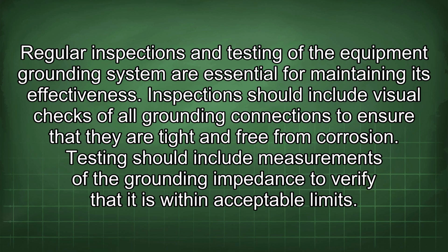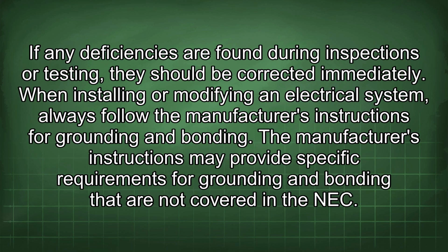Regular inspections and testing of the equipment grounding system are essential for maintaining its effectiveness. Inspections should include visual checks of all grounding connections to ensure that they are tight and free from corrosion. Testing should include measurements of the grounding impedance to verify that it is within acceptable limits. If any deficiencies are found during inspections or testing, they should be corrected immediately.